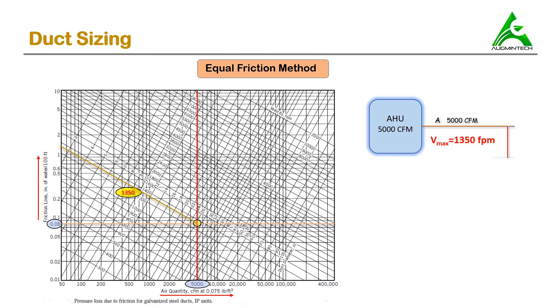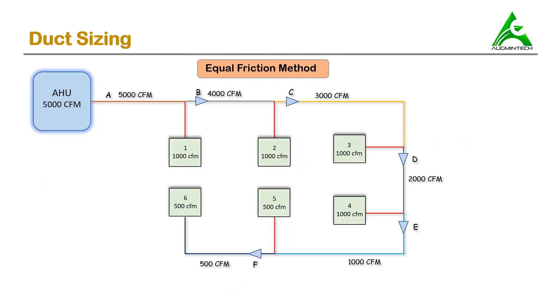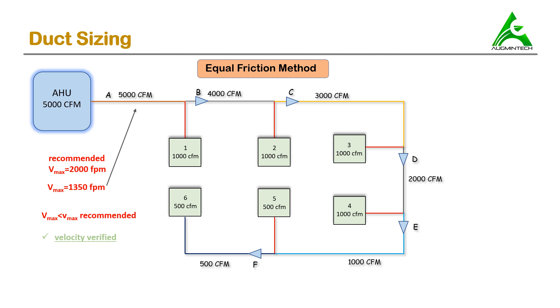The maximum velocity of air in our sample project is 1350 FPM, flowing in section A. The recommended maximum by Carrier for a library was 2000 FPM. Since 1350 FPM is less than 2000 FPM, the velocity test is verified. We don't need to check any other section because velocity only decreases further along the duct. This first verification step is now complete.